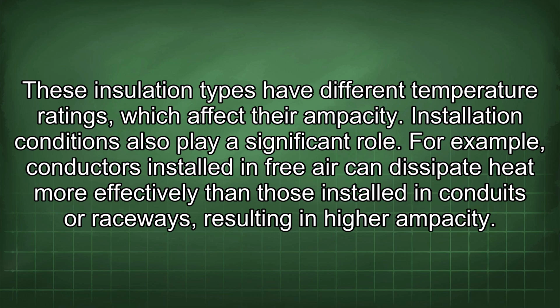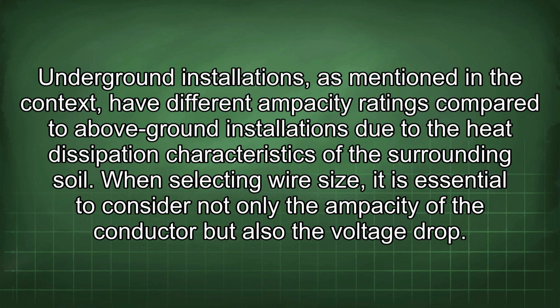Installation conditions also play a significant role. For example, conductors installed in free air can dissipate heat more effectively than those installed in conduits or raceways, resulting in higher ampacity. Underground installations, as mentioned in the context, have different ampacity ratings compared to above-ground installations due to the heat dissipation characteristics of the surrounding soil.